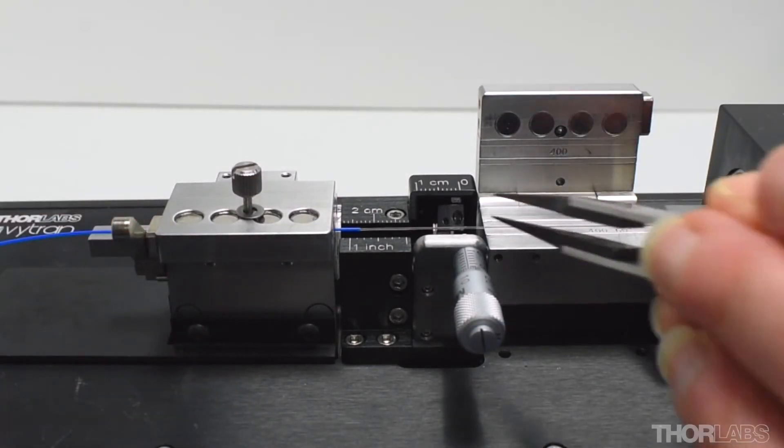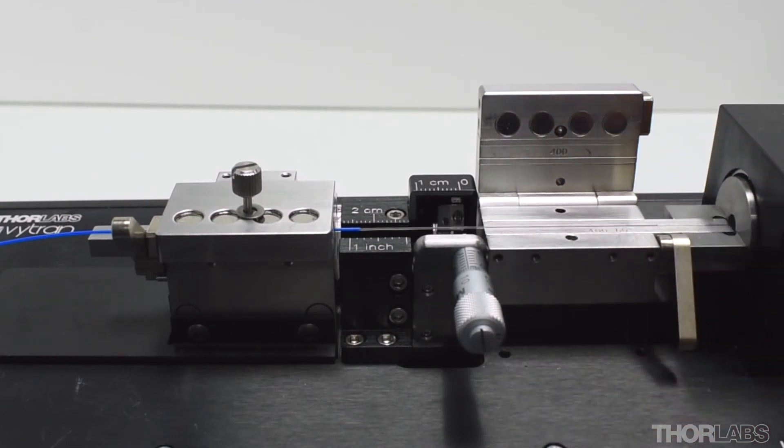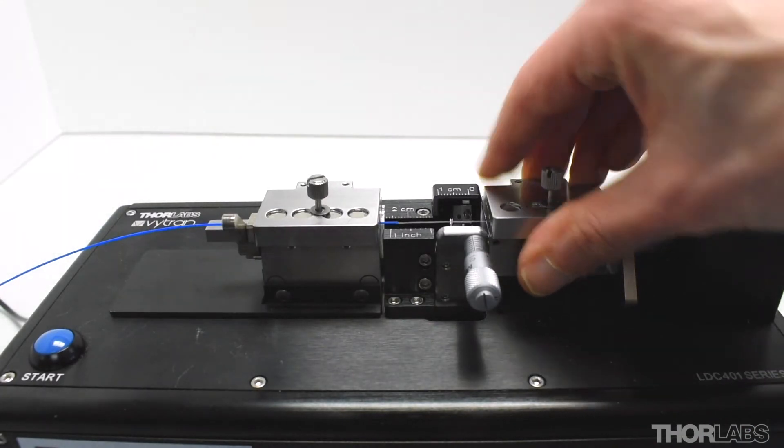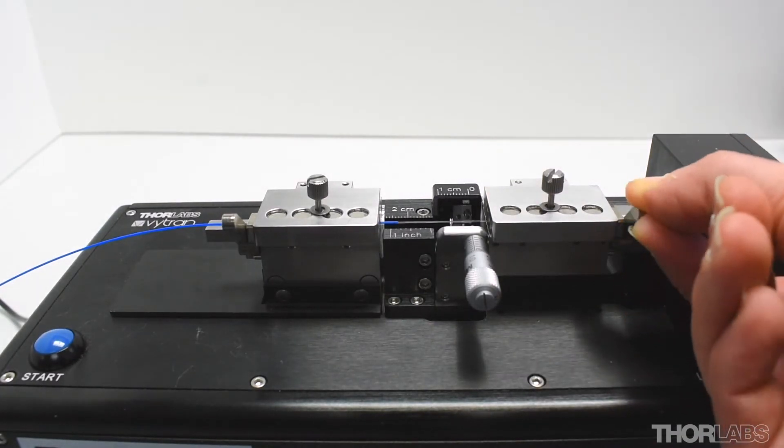Before closing the right lid, use soft tip tweezers to lift the fiber out of the right insert and allow the vacuum to draw it back into the V-groove. This will release any unwanted torsion caused as the fiber was loaded. Now lower the right lid and gently lift the cam lever to fully close it.